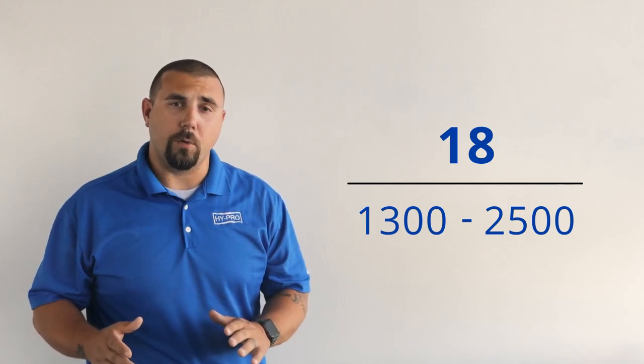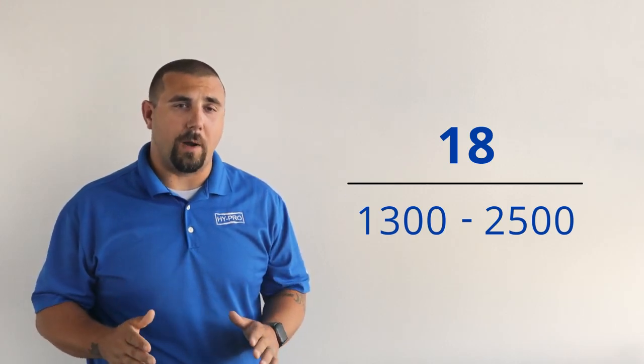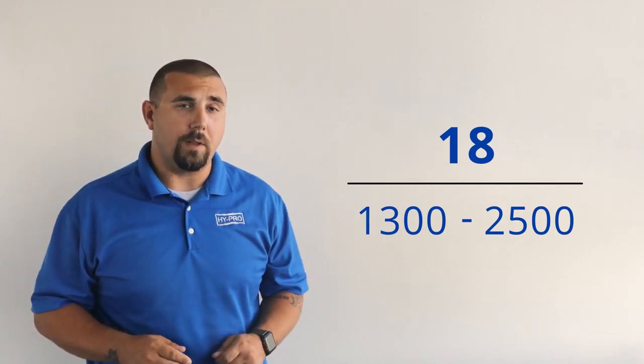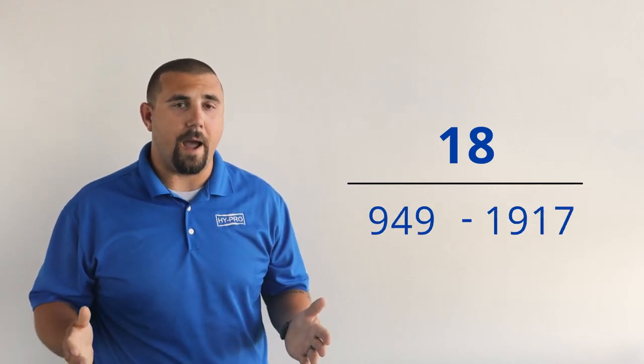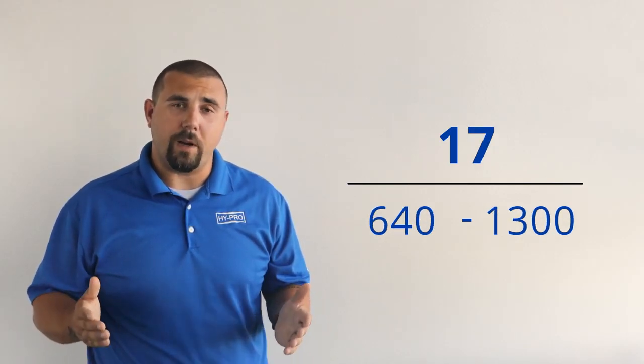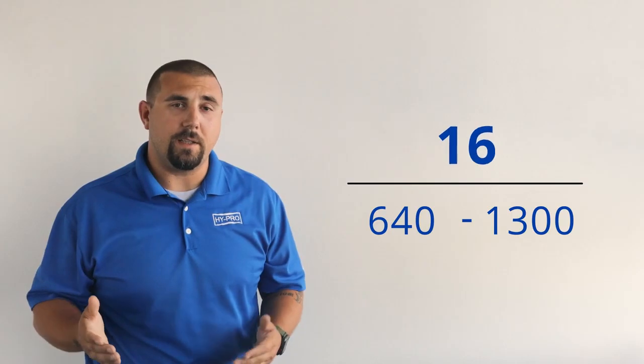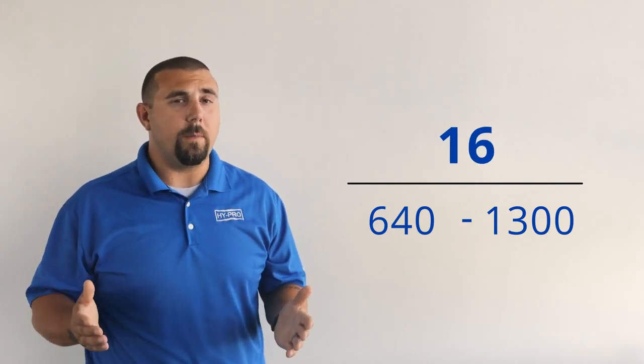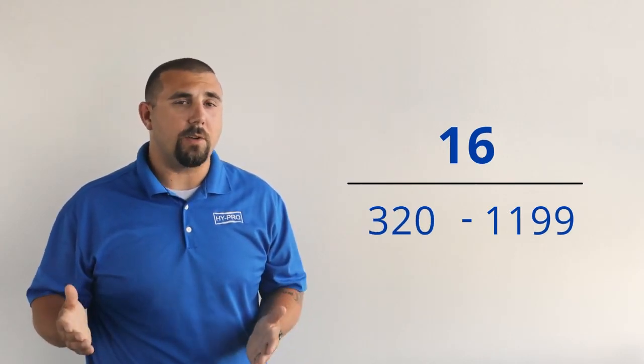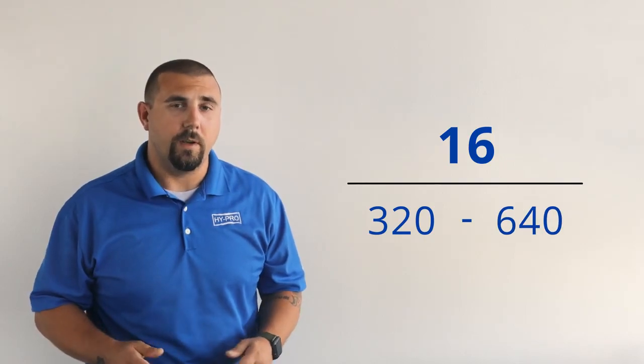Inversely, it also is important to know that as an ISO code drops by 1, the range of contaminant per milliliter of fluid is going to be cut in half. For example, if we have an ISO code that drops from 17 to 16, then we would only be between 320 and 640 particles of contamination per milliliter of fluid.